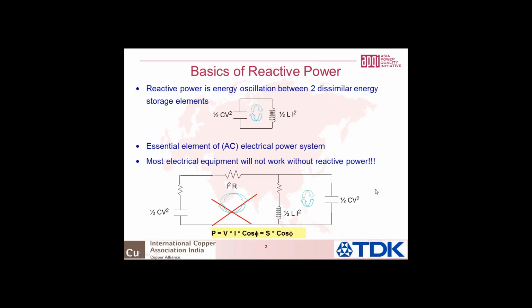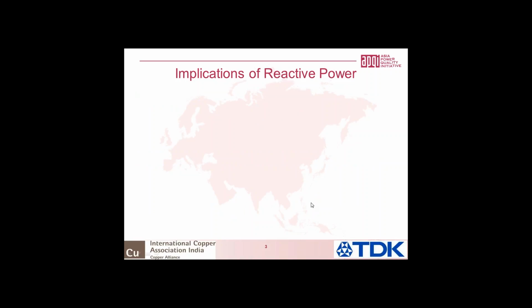And you know the very famous equation: the total power we deliver to the load is the product of volt ampere and power factor, which is the cosine of the angle between the voltage and current. Let's park it there and move on. As we know, if there is reactive power, if the power factor is not unity, the current in the system will increase.